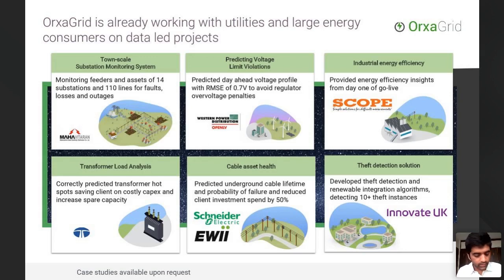So using big data for this Danish company, we were able to classify their entire cable sections into health index bands between 1 to 5. Health index 5 is best - you don't need to worry about it or even look at it. Health index 1 is the most dangerous, requiring immediate maintenance. Once you have this classification done, you can take your specialized maintenance tools like your CFL van or partial discharge monitoring equipment, and monitor only those lines that are in the riskiest cable sections.